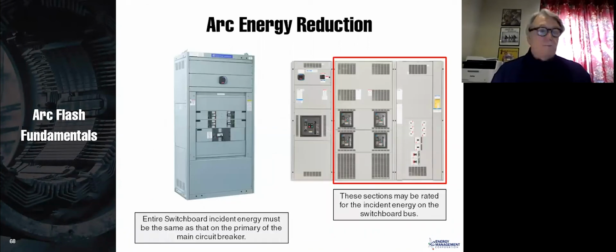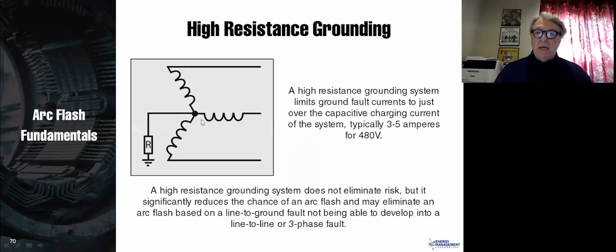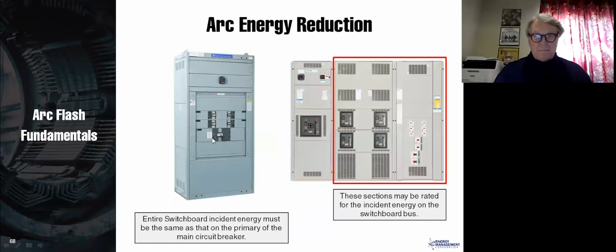Let's go here. If you have a panel like this and you have an arc flash, and let's pretend this is your main breaker. It may or may not be on this panel, but what is your arc flash? It'll be the arc flash coming in to that panel. It will not be the arc flash on the secondary side of that main breaker.